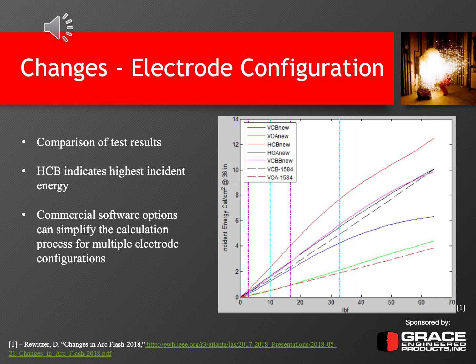And as you go down farther and farther, you also have the vertical open air. So the vertical open air is probably the least severe based on this graph, followed by the VCB as the next least severe. And the one that's really important is if there is an HCB configuration, that's something you definitely want to look at and include in your arc flash study, because that could significantly change the incident energy calculations as shown by this plot.